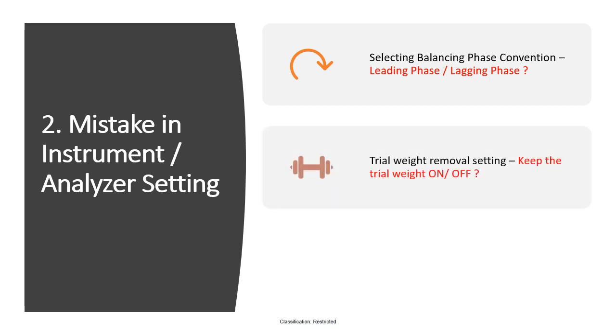The next setting is the trial weight removal setting. During balancing, the analyzer may ask whether to keep the trial weight on or off. If you select 'off,' you must remove the weight from the rotor. Sometimes this step is missed, or the wrong setting is selected and the trial weight is left on the rotor, which will not give the desired result.